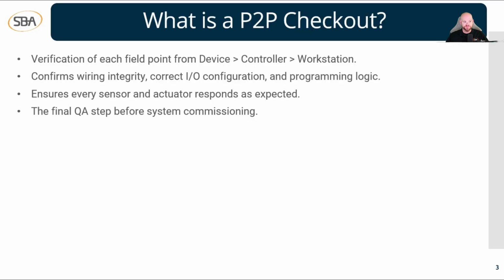Simply put, a point-to-point checkout is just the verification of each field point from device to controller to workstation. We're basically just verifying that all of our hardware points are working. So this could be temperature sensors, relays, actuators. It could even be programming logic. If we've already set it up, we're going to test all this stuff and make sure that it's working correctly.